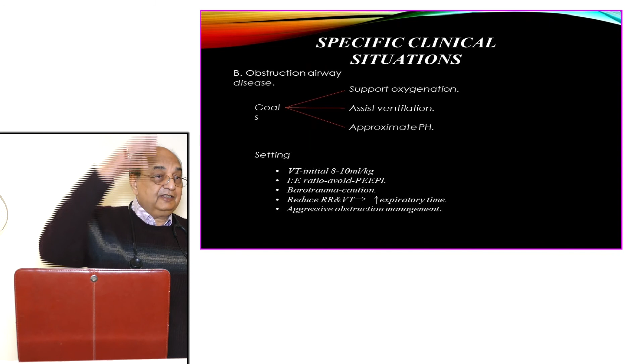If there is an obstruction anywhere, whether it is inspiratory or expiratory, as a general rule, if there is an inspiratory obstruction, you increase the inspiratory period. If there is a low compliance, you increase the pressure. But if there is obstruction, you increase the period. By increasing the pressure, you cannot bypass the obstruction. You cannot get the objective by increasing the pressure. It means you will have to increase the period.